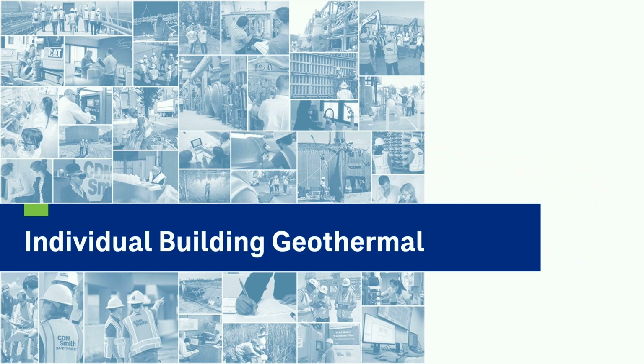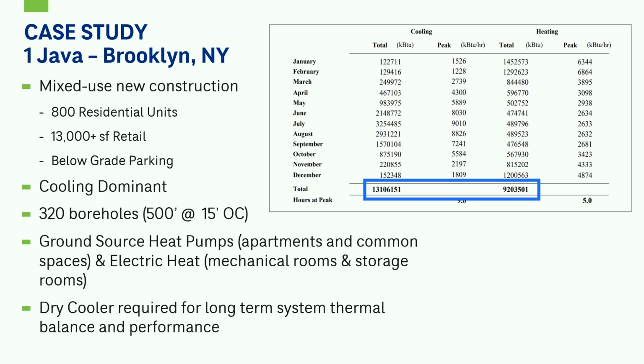So then we'll go through another example of an individual building. This is for some of you who may have gone on the tour yesterday for One Java in Brooklyn, New York. It's a mixed-use new construction building with 800 residential units, over 13,000 square feet of retail, and below-grade parking. And of those 800 residential units, 30% are for affordable housing. So in the loads on the right, you can see that we're now cooling dominant, even though it's a residential building, because it had some of those energy efficiency measures in there. So now it's become more of a cooling dominant building with about 13 million kBTUs compared to about 9 million kBTUs for heating.